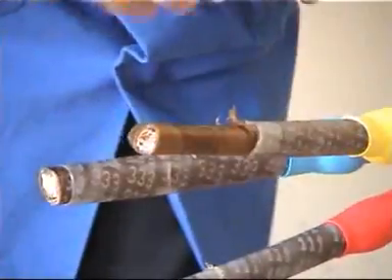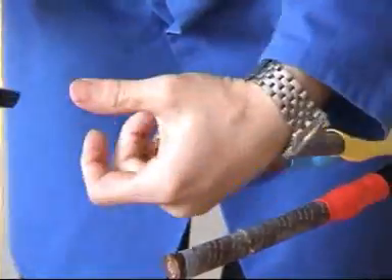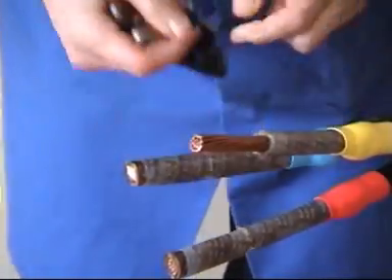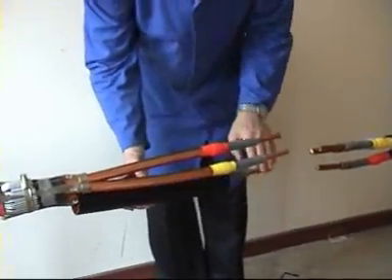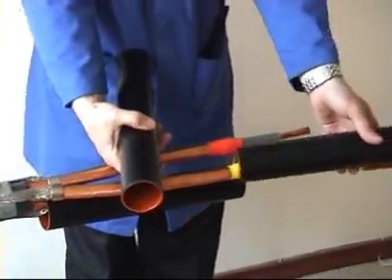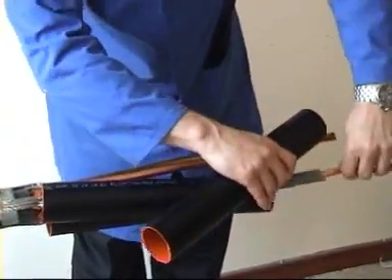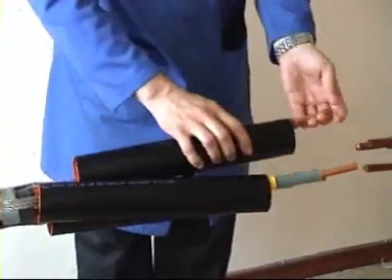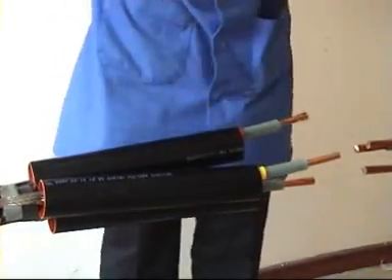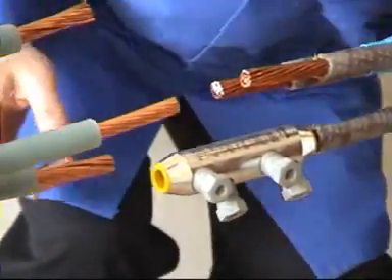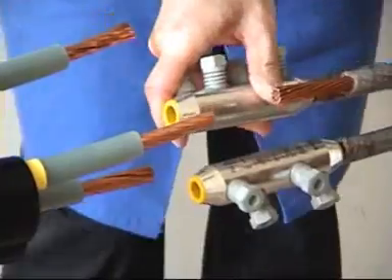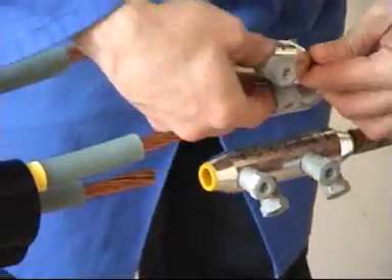Mark out the cores, remove the insulation, ready for the connectors. Before fitting the mechanical connectors, position the connector insulation tubes down the cores. Here we're using mechanical shear bolt connectors that are tapered with conductors centralised. Crimp compression ferrules can also be used.